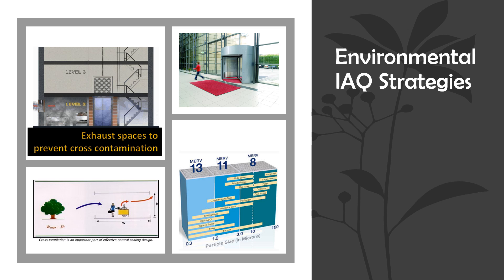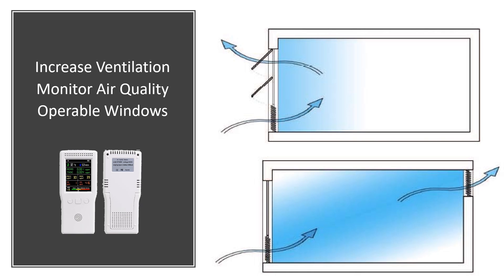Third and fourth, you must use ventilation filters that are at least MERV 13 or higher for filtering outdoor air or recirculated air. Fifth, you can increase the ventilation by 15% above the minimum rate in the prereq. Or sixth, you can increase the ventilation by 30%. Seven, you can have operable windows in 75% of the regularly occupied spaces.